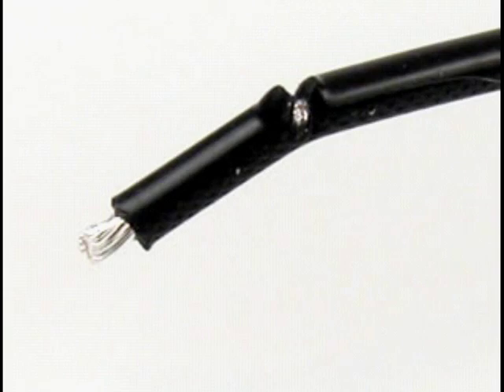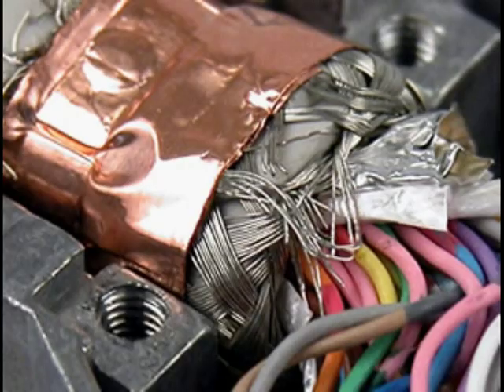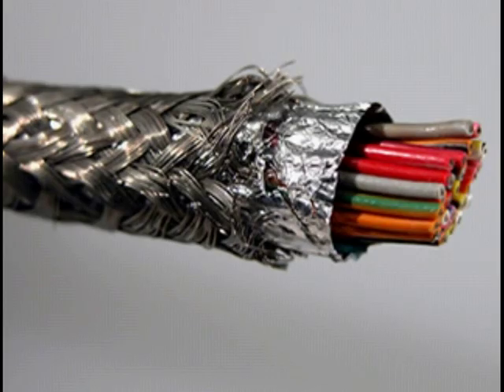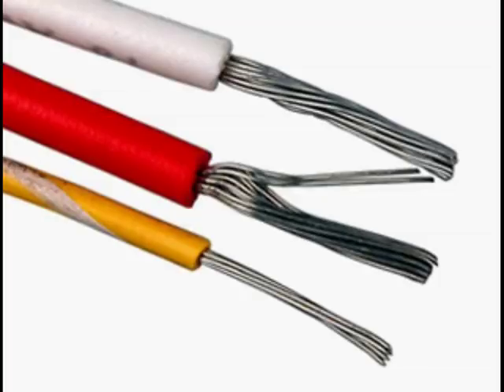But in many instances, you may have nicked insulation, stray wires, braided shielding, or contaminants such as solder flux, that can cause wires to be very close, but not actually dead shorted to each other.